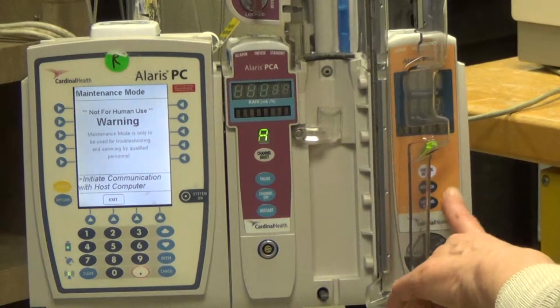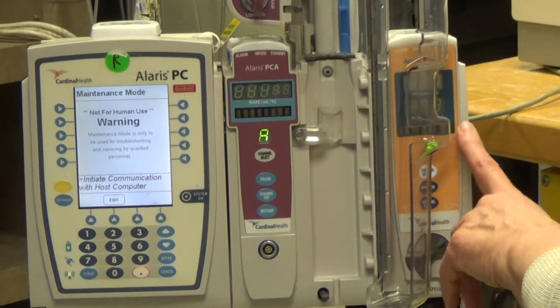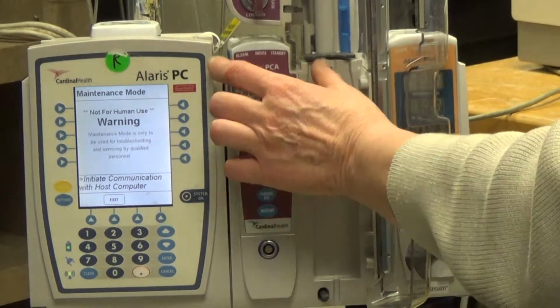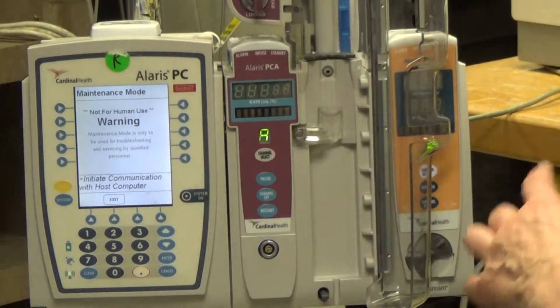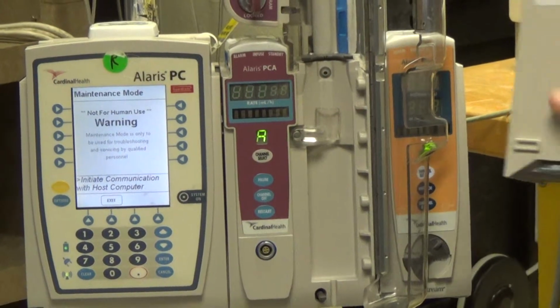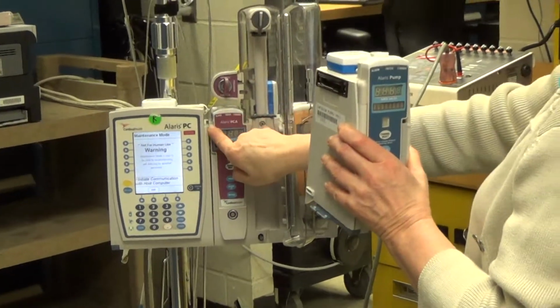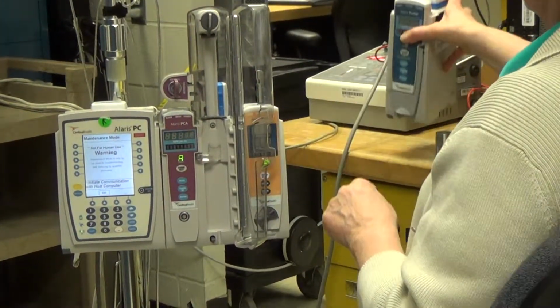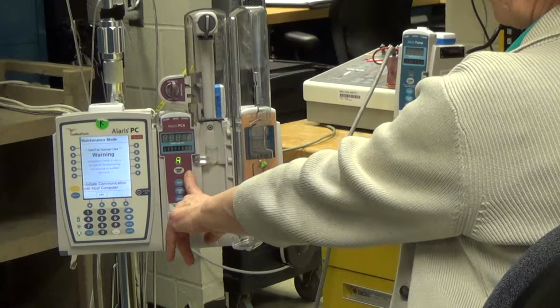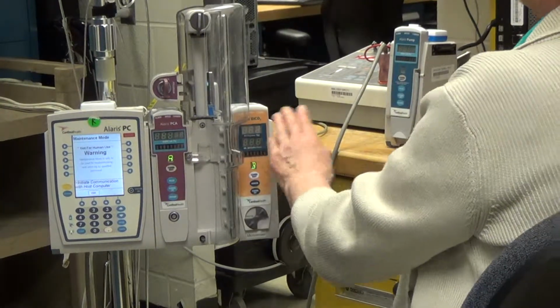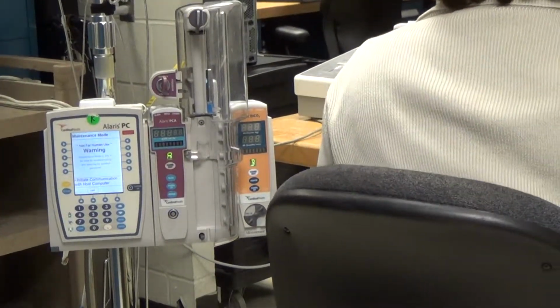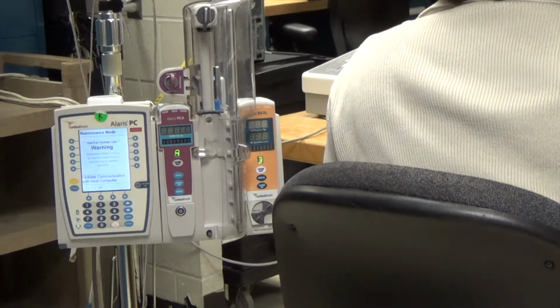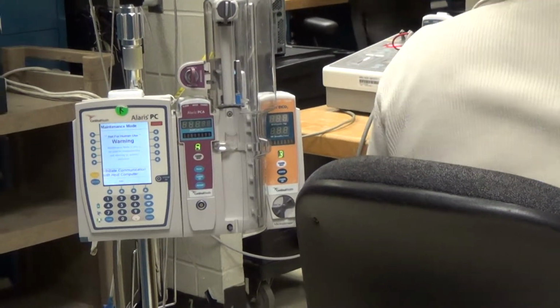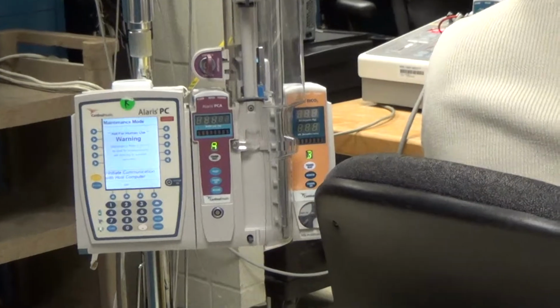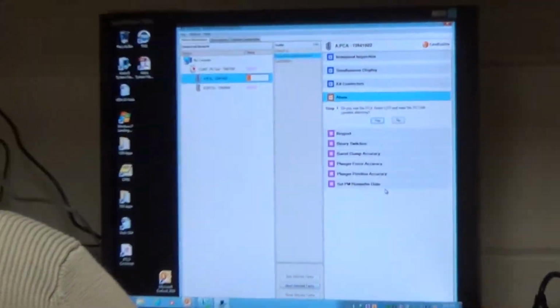Now it calls that we have to have at least one other device attached. This is to make sure that these IUI connectors that I showed you here are working correctly, so that both of them are usable, and to make sure that even if we use one pump here, the next one will still be functional. Moving on. Now we see here on our screen that all three devices are detected, and we move on to the next one.